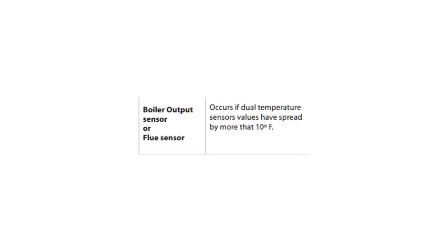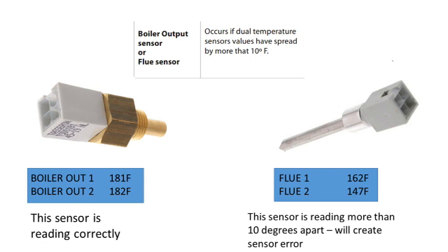We need to determine which sensor is giving us the problem and determine if it is actually a bad sensor or possibly something else causing the issue. Let's say we have come across a boiler output sensor or flue sensor fault. We see this occur if dual temperature sensors have spread by more than 10 degrees. It means these two particular sensors are both redundant sensors — they read the temperature twice, and if those two readings are more than 10 degrees apart, we get a sensor error.